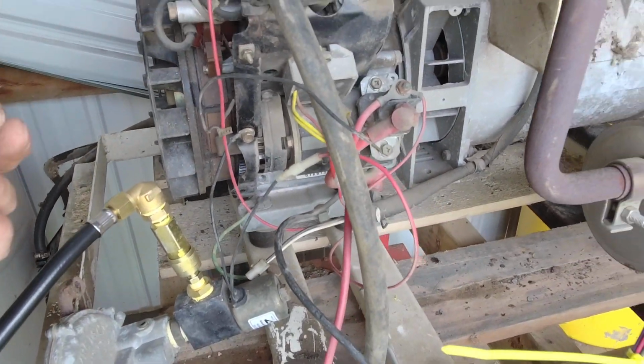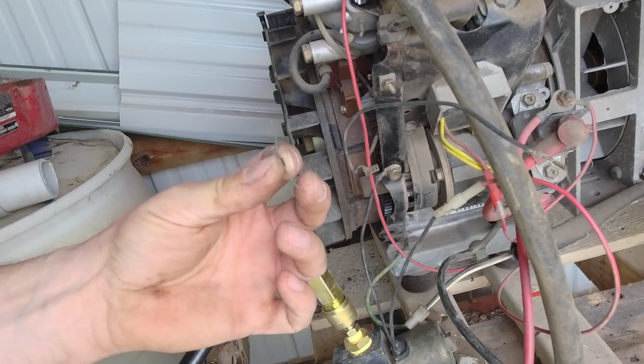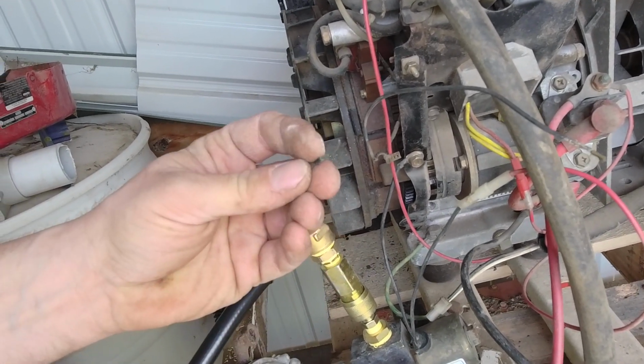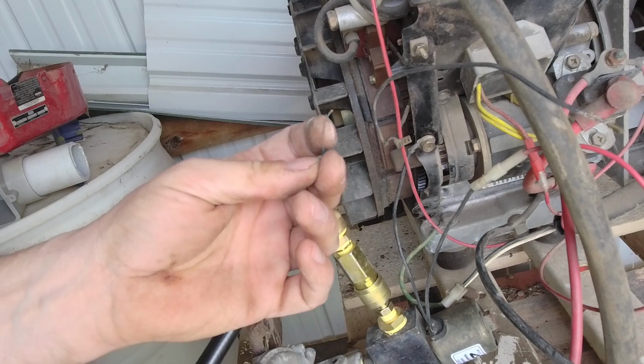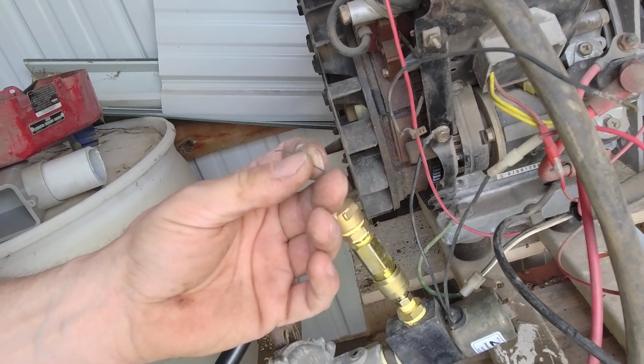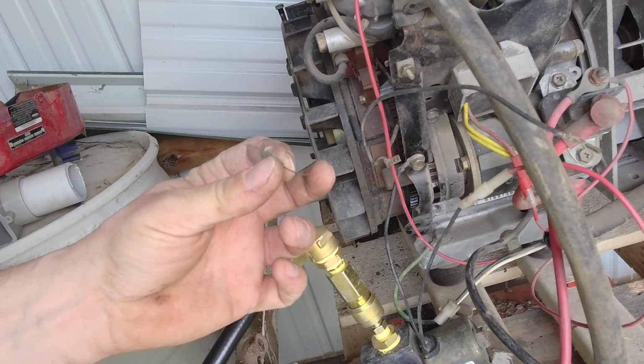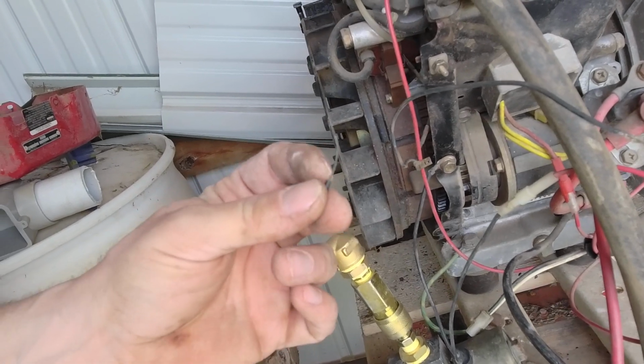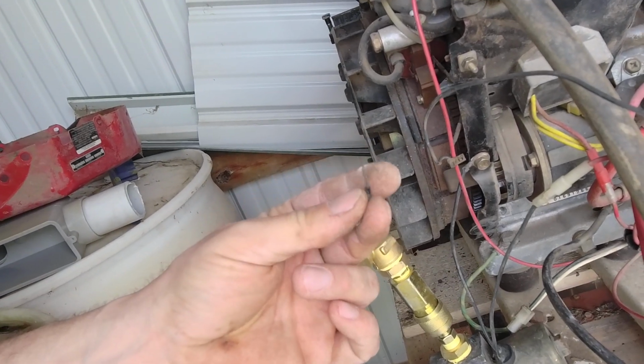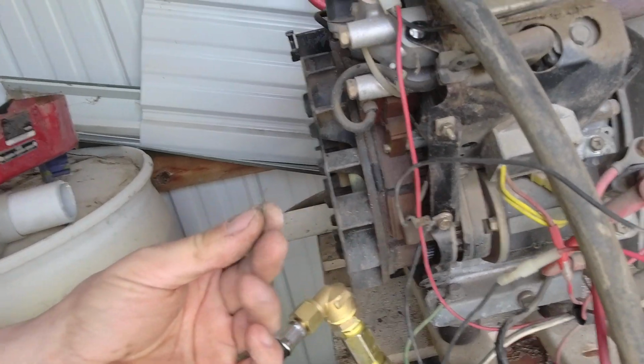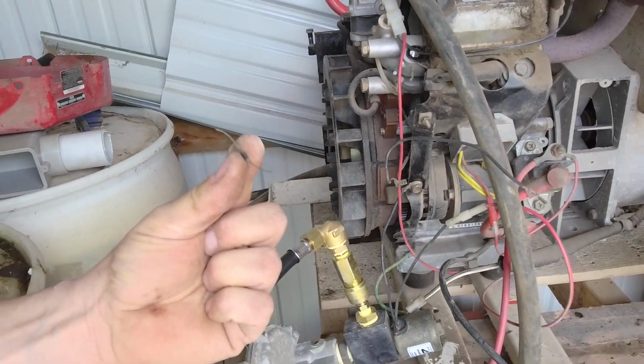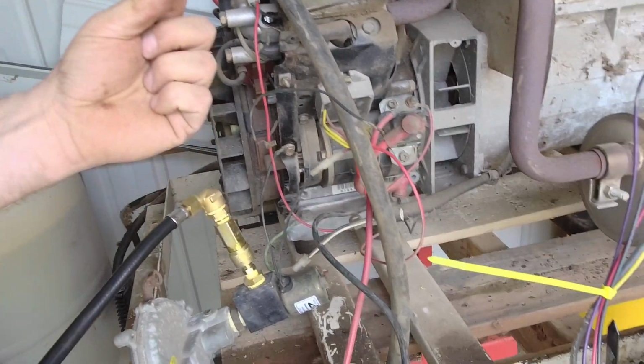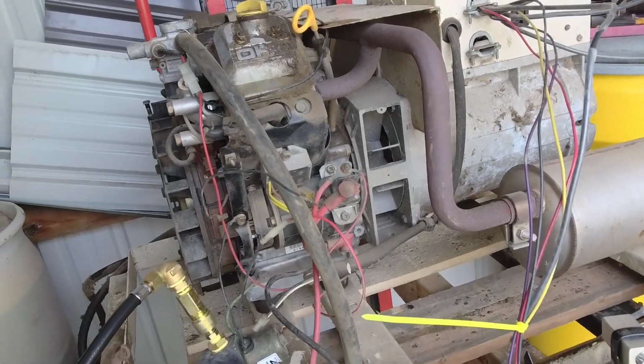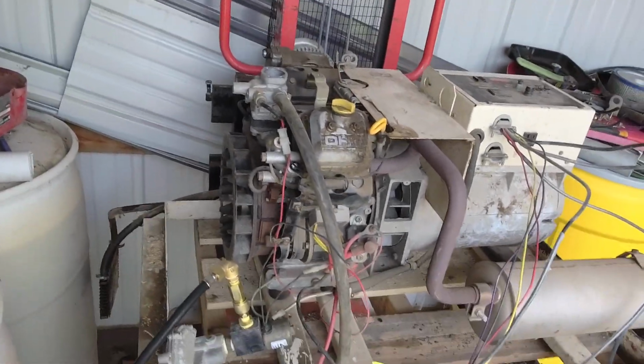Effectively killing the motor, not allowing it to run. All the insulation on this wire was rubbed off or chewed off, and the bare copper, you see how it's all corroded and oxidized and green, it's been that way for a long time. So I have to imagine this right here is probably why this whole unit got swapped out with a new one, and this ended up on Facebook.